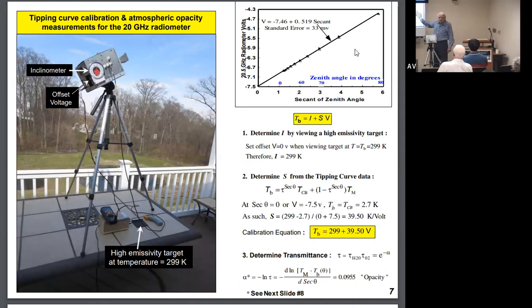So you have another point in your calibration. Therefore the slope in that equation comes from 299 minus 2.7, that's the cosmic background, divided by 0, which is your offset, and 7.5 volts is what you measure. See, minus 7.5, that's why it's positive, because it's minus. And there is your slope, which is the most important thing to get.